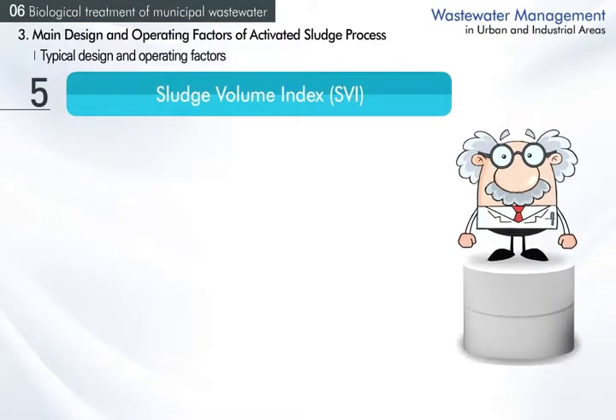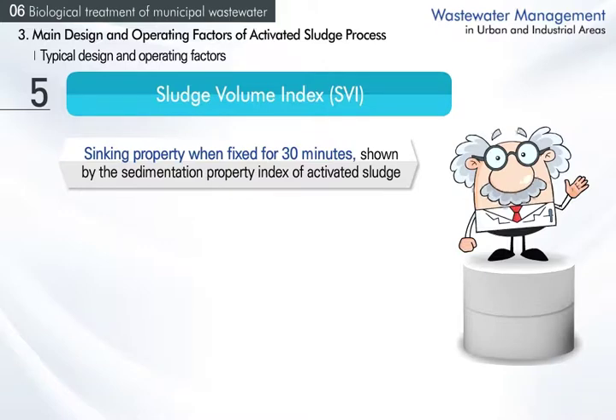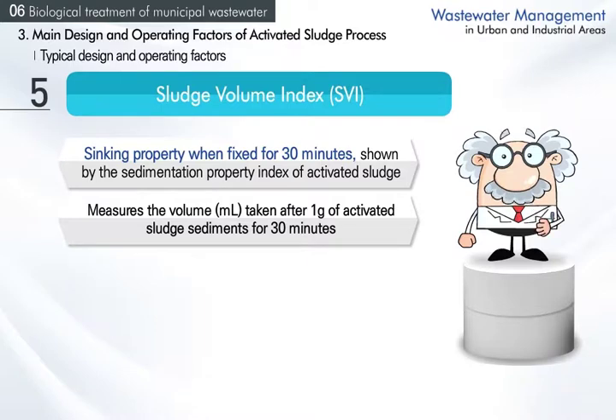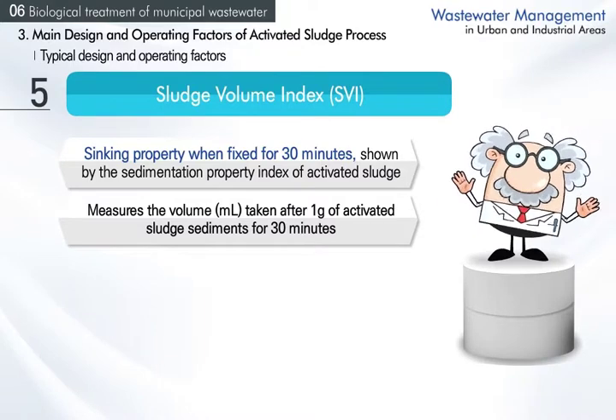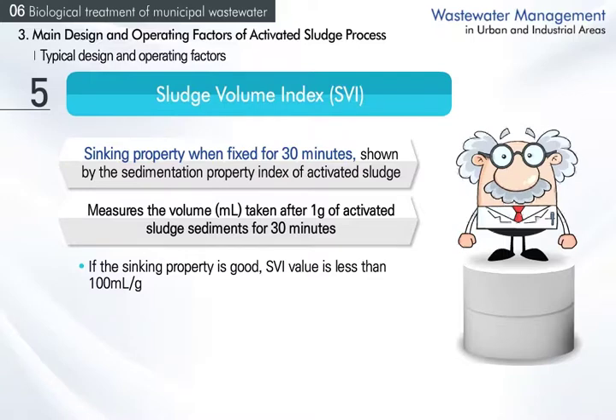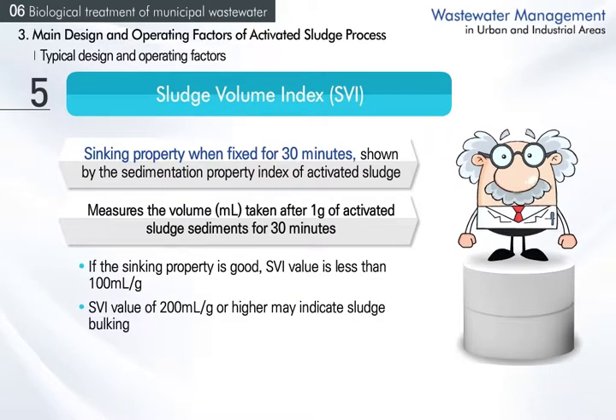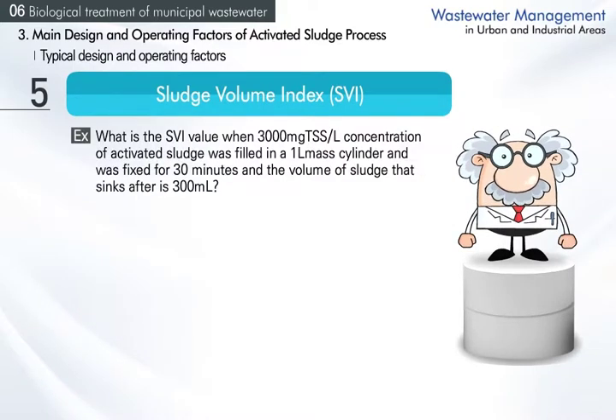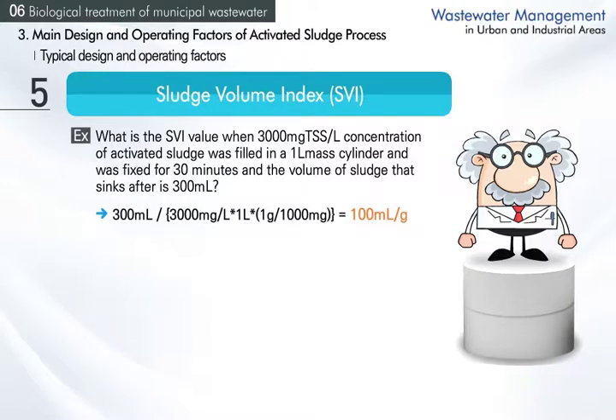Sludge volume index (SVI) is an index that shows the sedimentation property of activated sludge, expressing the degree of sinking when activated sludge is settled for 30 minutes. It is calculated by measuring the volume taken after 1 gram of activated sludge sediments for 30 minutes. If the sinking property is good, SVI is less than 100 mL/g, and an SVI of 200 mL/g or higher may indicate sludge bulking. For example, with 3,000 mg TSS/L concentration in a 1-litre cylinder fixed for 30 minutes, SVI can be calculated as 100 mL/g.